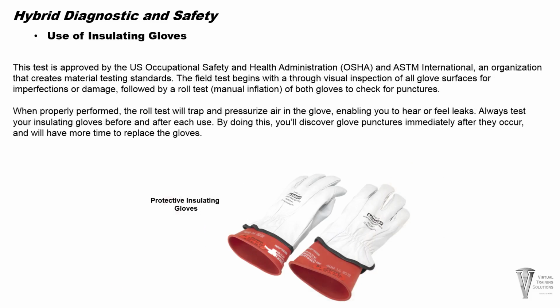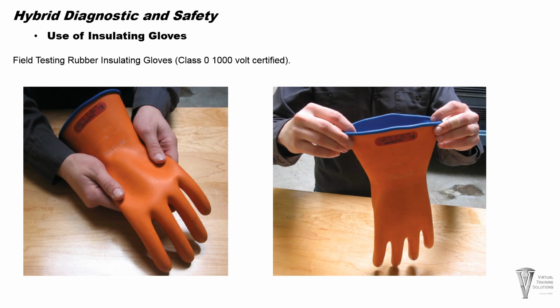Some manufacturers advocate a puff test, blowing into the glove to inflate it and check it for leaks. Although professional inflators are available, the most common approved field test is to trap air in the glove itself, then roll the cuff tightly to inflate the working area of the glove. Let's see how this is done. Visually inspect both insulating gloves inside and out for any flaws or damages. Especially check the expiration date. Using both hands, hold the insulating gloves by the edge of its cuff and let it hang naturally. Pull the cuff tight to trap as much air into the glove as possible. Keeping the cuff sealed, lay the glove on a clean, dry, horizontal surface with the fingers pointed away from you and start rolling.